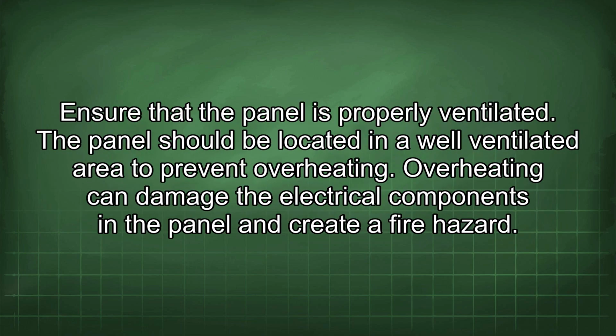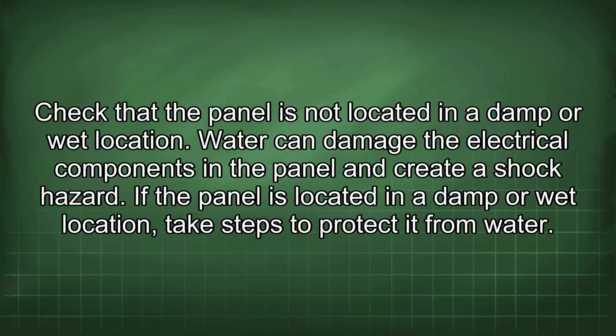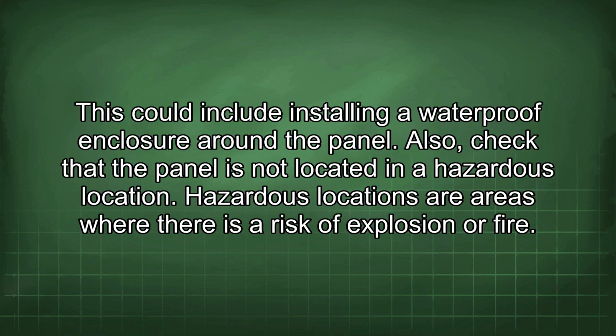Ensure that the panel is properly ventilated. The panel should be located in a well-ventilated area to prevent overheating. Overheating can damage the electrical components in the panel and create a fire hazard. Check that the panel is not located in a damp or wet location. Water can damage the electrical components in the panel and create a shock hazard. If the panel is located in a damp or wet location, take steps to protect it from water. This could include installing a waterproof enclosure around the panel.